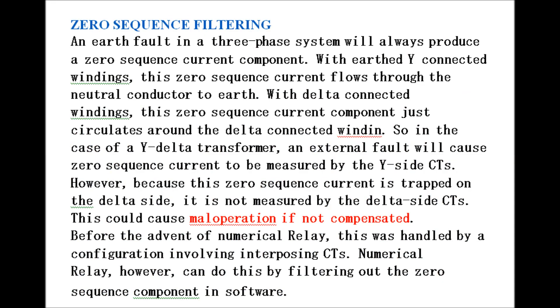Zero-sequence filtering: an earth fault in a three-phase system always produces a zero-sequence current component. With an earth Y-connected winding, this zero-sequence current flows through the neutral conductor to earth. With a delta-connected winding, this zero-sequence current component circulates around the delta winding. In the case of a Y-delta transformer, an external fault causes zero-sequence current to be measured by the Y-side CT; however, because this zero-sequence current is trapped on the delta side, it is not measured by the delta-side CTs. This could cause mal-operation if not compensated. Before numerical relays, this was handled using interposing CTs. Numerical relays, however, can filter out the zero-sequence component in software.